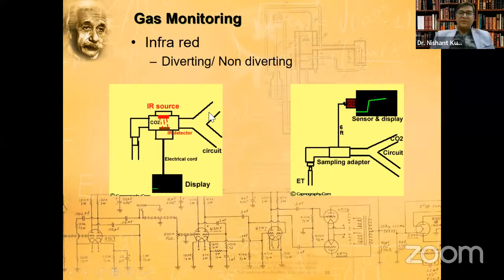gas present there. As we all know, this is the patient circuit. The patient exhales from this, CO2 passes through this, and there is a continuous bombardment of the infrared wavelength which is detected by this. Based on the concentration of the absorbed wavelength, we have this display on the monitor.